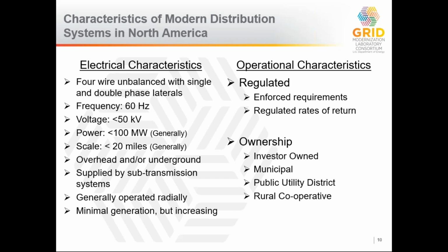Voltages at the distribution level are typically less than 50,000 volts. More like 12,000 is much more common. Power levels, when you're talking distribution level equipment, less than 100 megawatts. And for a distribution circuit, power only goes less than 20 miles. There are exceptions, but these are good rules of thumb.